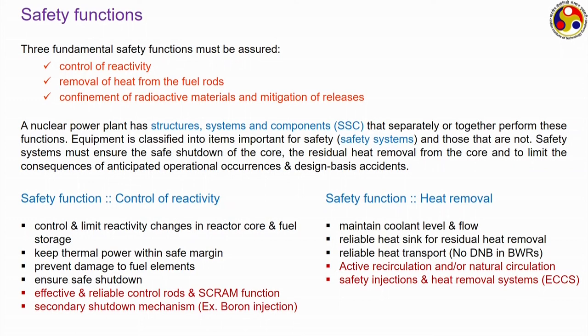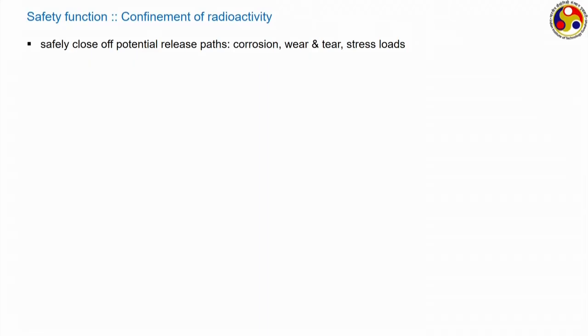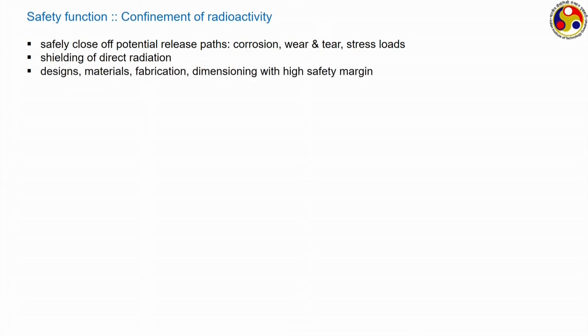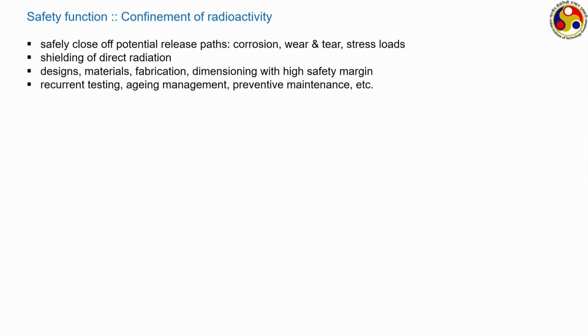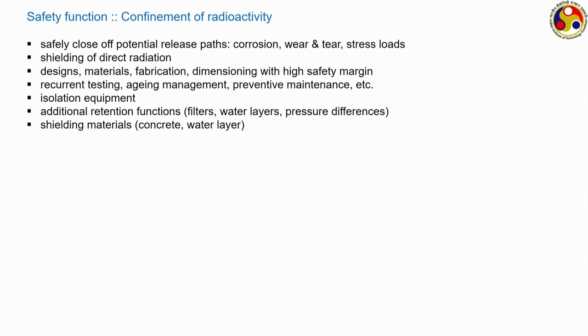Confinement of radioactivity involves closing all potential release paths against corrosion, wear and tear, and stress loads. Shields must be provided against direct radiation, with high safety margin in design, material, fabrication, and dimensioning, along with recurrent testing, aging management, and preventive maintenance. Additional retention functions like filters, water layers, and isolation equipment also contribute to confining radioactivity. Shielding materials include several levels of concrete and water layers — water has a reasonably high neutron absorption cross-section, helping reduce reactivity inside the core.